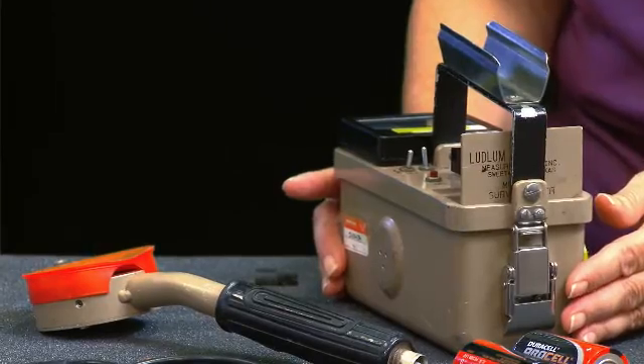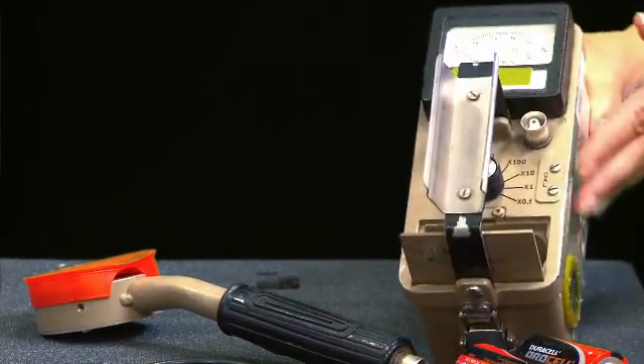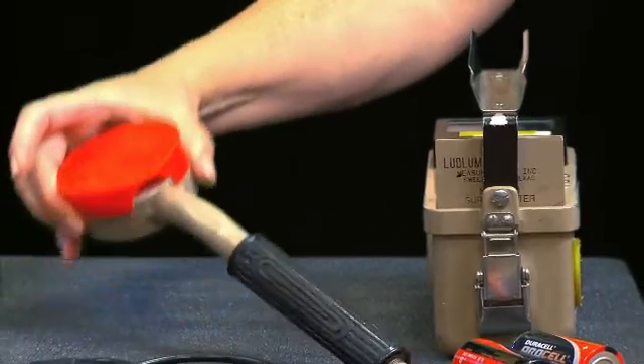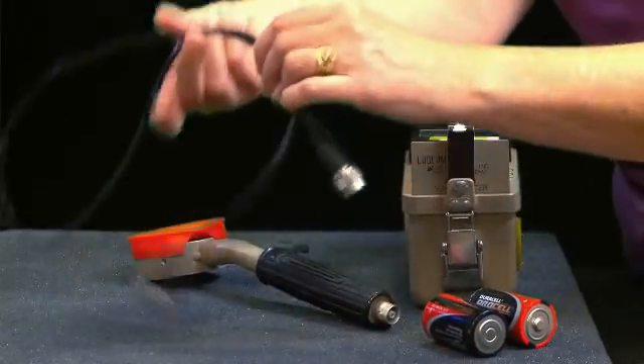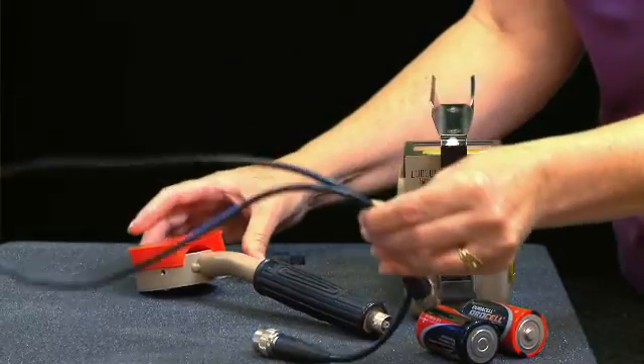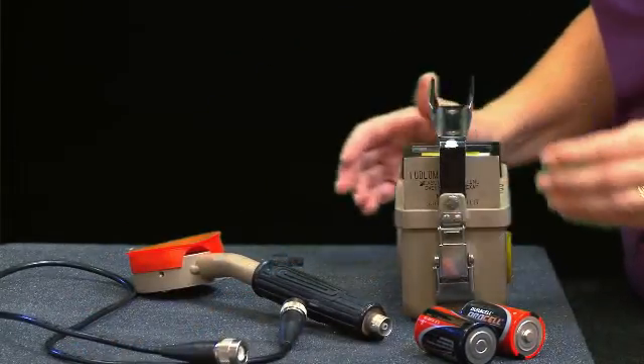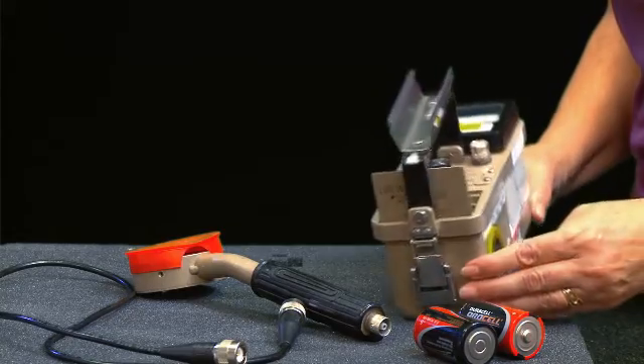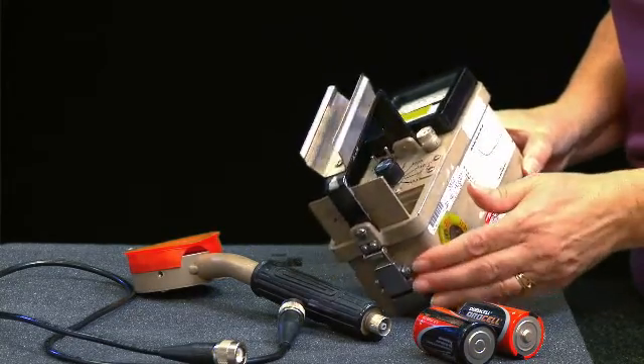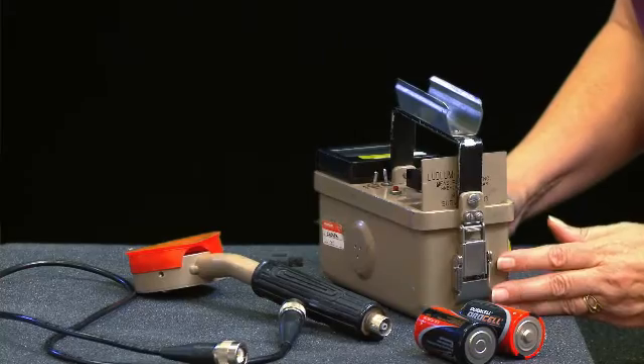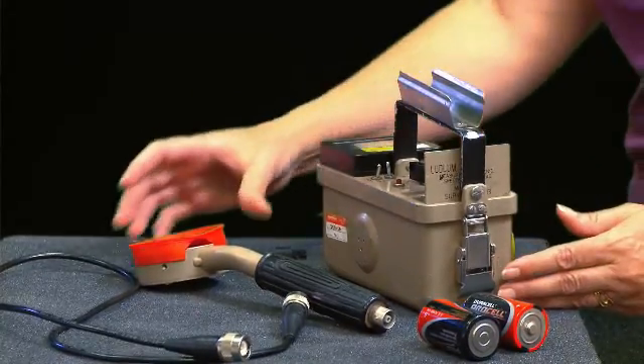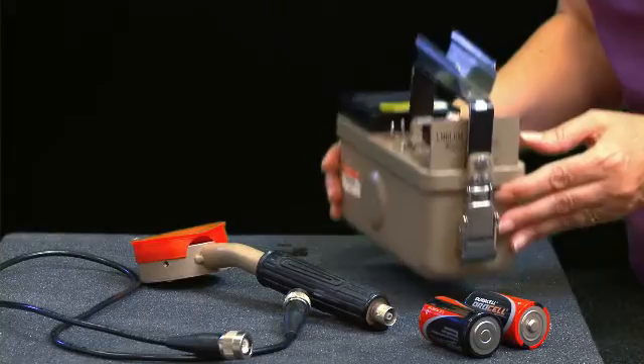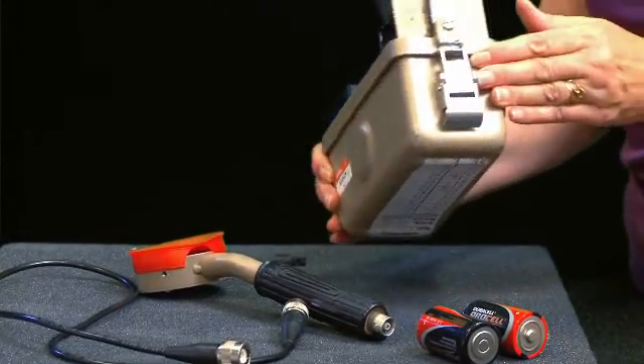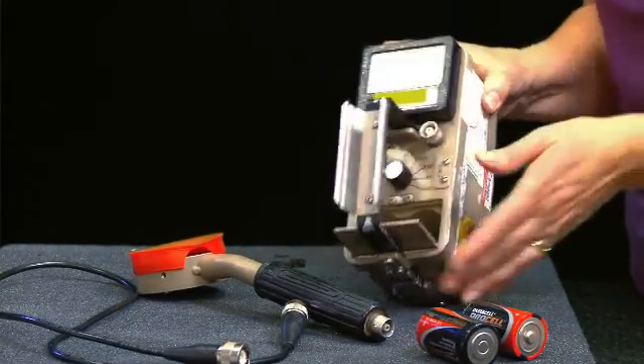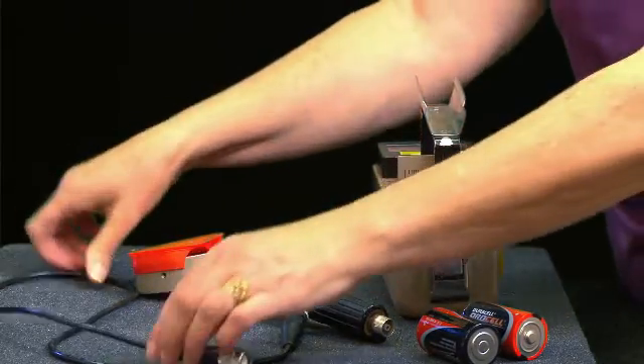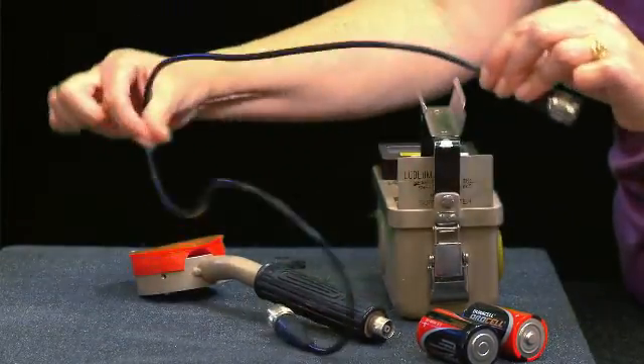survey instrument. In the kit, you have the meter, the probe, and a cable. Prior to assembling the unit, make sure that it has been calibrated within 1 year of use. This information is provided on the side of the meter. Begin by examining the integrity of each component. First, look at the survey meter and check that it is intact. No dents on the corners or cracks on the display. Next, examine the cable for any obvious damage such as cracks or crimps.